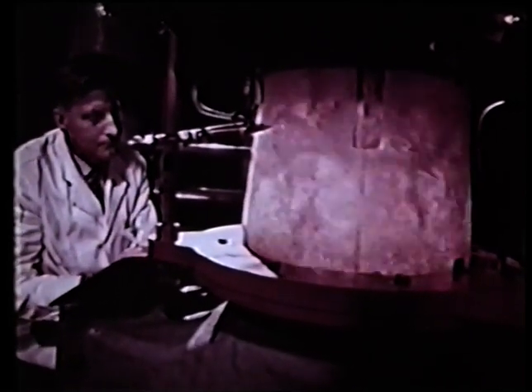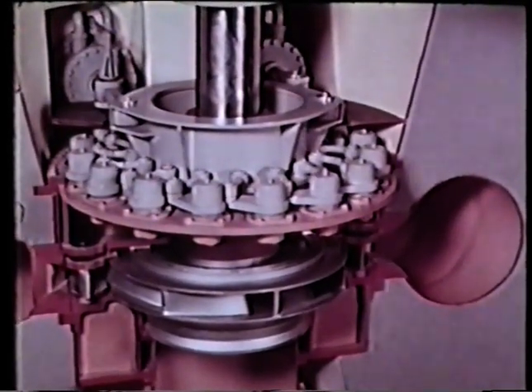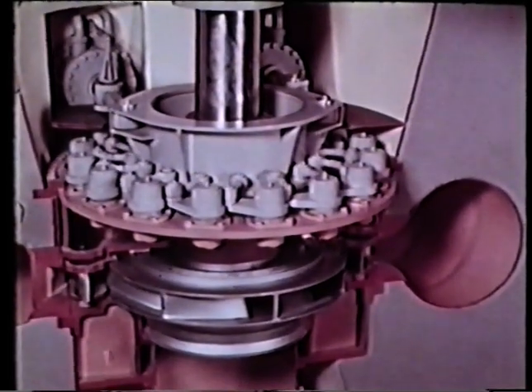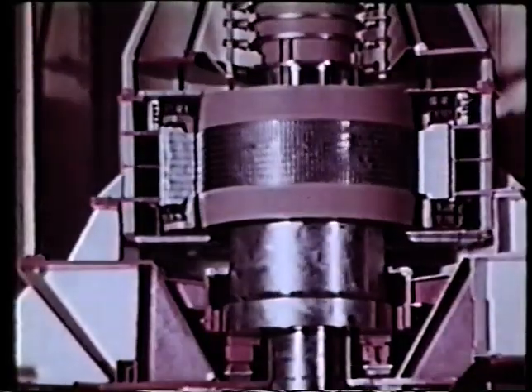Starting as a pump means studying the conditions in the runner when the suction cone is only partly water-filled. The starting pony motor, 1/10 the size of the main motor beneath it, cannot start a pump full of water. The water must first be blown down clear of the runner with compressed air, till the water drag is reduced to windage.